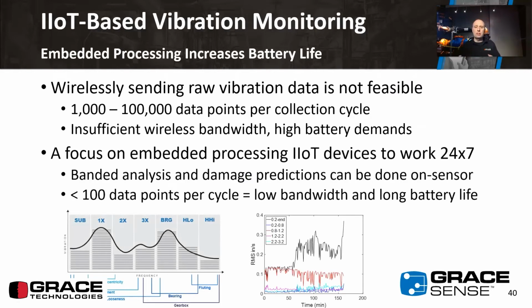So by focusing on processing data before we send it, we can allow these Internet of Things-based devices to work 24/7. The way this typically works is that banded analysis we talked about, breaking things down into individual bands, can actually be done right on the device itself. Your sensor's there, you've got a processor there, it captures that data, processes it down, and breaks it into these bands. If we do that all on the sensor, instead of sending 10,000 or 100,000 data points per cycle, we can send, in the case of Grace, 65 data points per cycle.